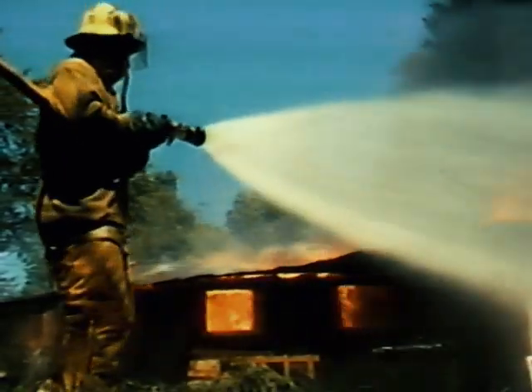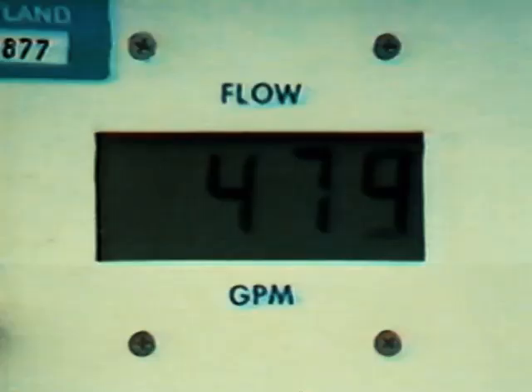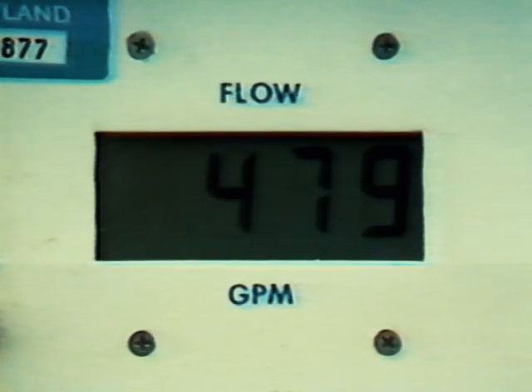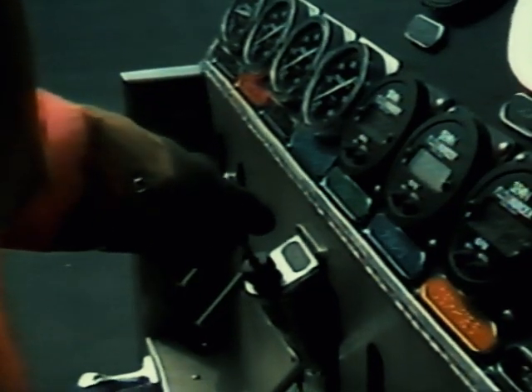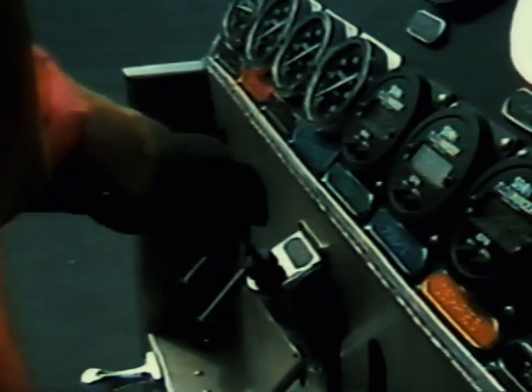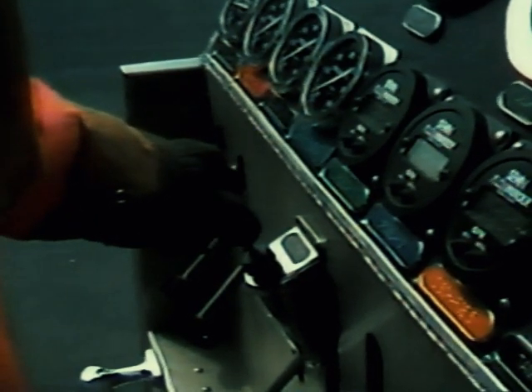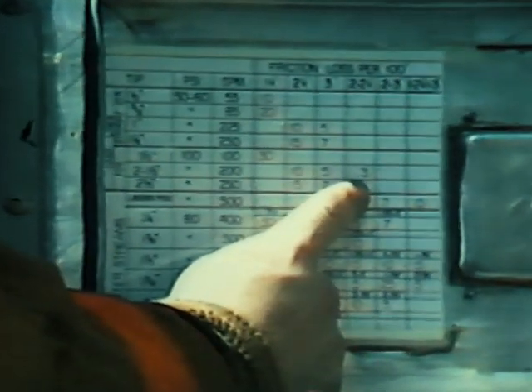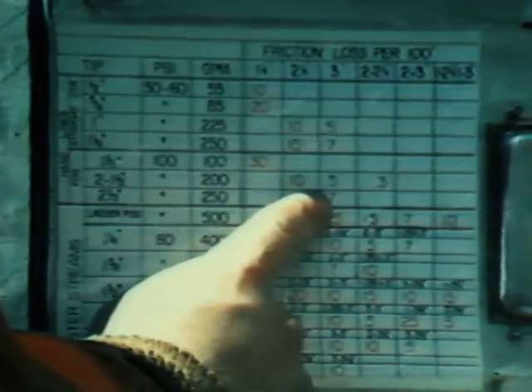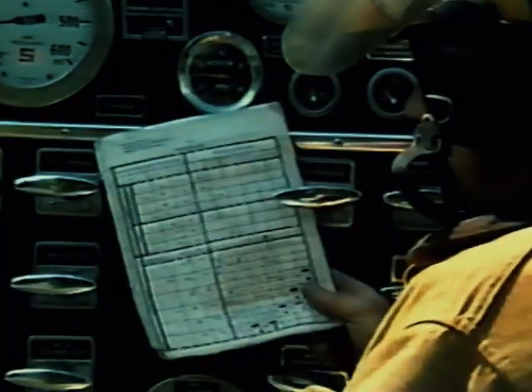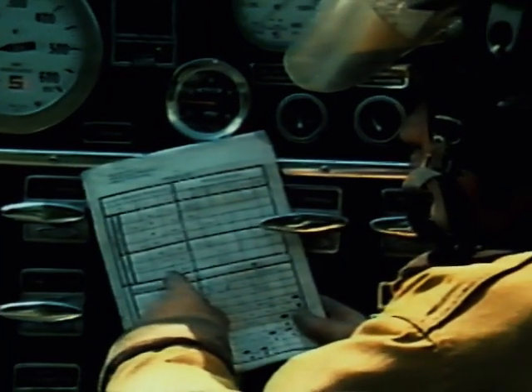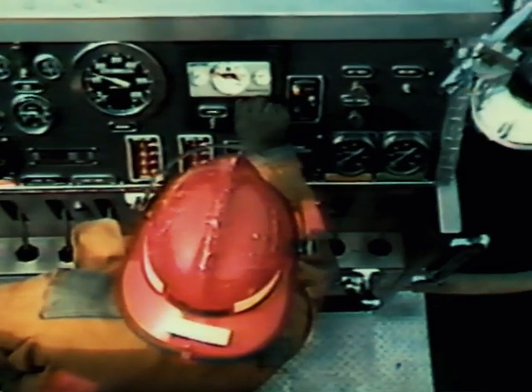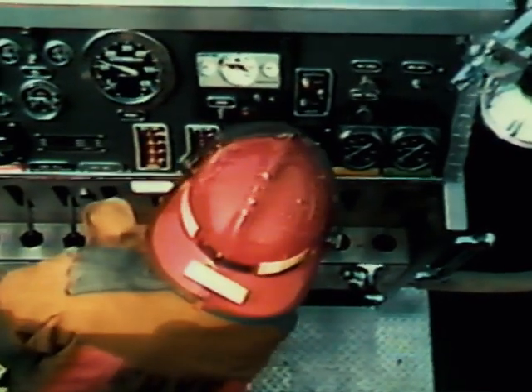To maintain the proper quantity of water to the nozzle, watch the flow meter at the discharge, and adjust the speed of the pump with the engine throttle to maintain the required water flow. Flow meters do not eliminate the need to understand firefighting hydraulics or the necessary math calculations used at the fireground, but they will reduce the number of calculations you need to make.